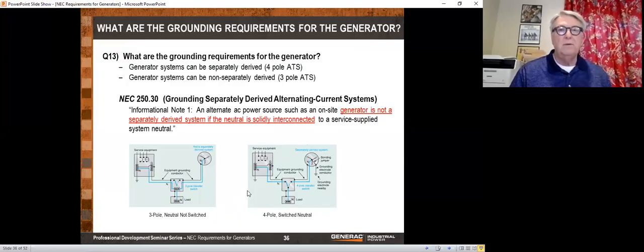Grounding and ground fault, this is question 13. What are the grounding requirements? Well, we talked about this with transfer switches, but for those of you who may have forgotten or who didn't listen to that, we have 3-pole and 4-pole transfer switches. Now, I'm only talking about 3-phase right now. If you have a 3-pole transfer switch, then you have a neutral bus bar. And basically, the generator neutral is connected to the system neutral in that neutral bus bar. And so your neutral to ground bond occurs at the service. And you do not have a neutral to ground bond at the generator.